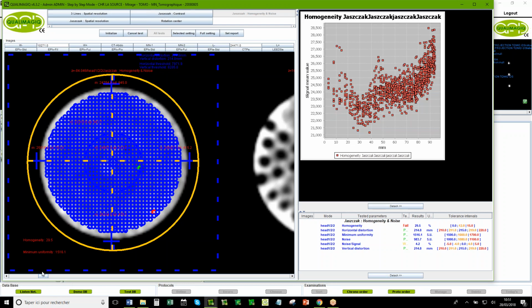Finally, the quality of an imager is all the time the spatial resolution, the contrast, and the homogeneity. You have this test on all imagers, also a camera, also a television. And another test is geometric distortion. So when you evaluate an imager: geometric distortion, homogeneity, spatial resolution, and contrast are the most important parameters.